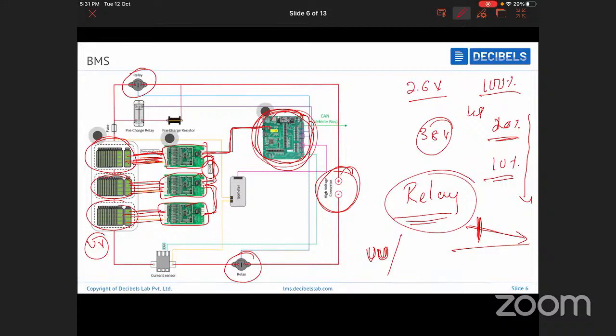The concept of contactor welding is this: you have to check if the contactor has been welded. If you know the relay circuit, there's a switch side and a coil side. For a bad instance, when the contactor got a high current and voltage, it might have welded, meaning it has got permanently contacted. So when the BMS asks it to disconnect, it wouldn't disconnect. Now the scenario is already in an on stage, without even getting a signal from the battery management system. That scenario is called contactor welding, and you need to monitor all these things.